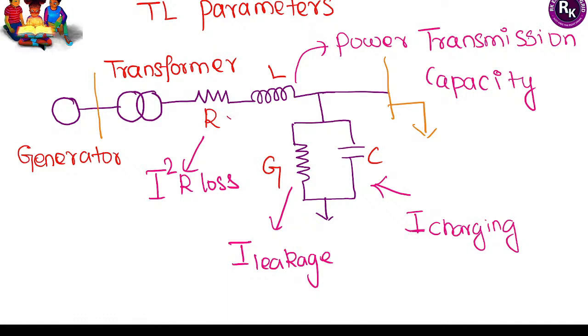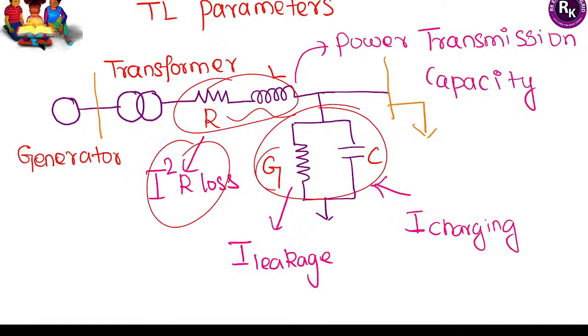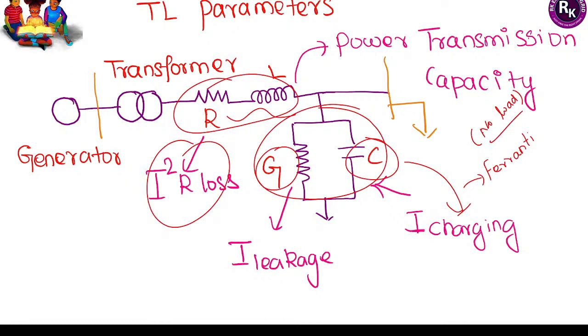Transmission line parameters: the equivalent circuit of a transmission line has four important parameters — series parameters (resistance and inductance) and shunt parameters (conductance and capacitance). Capacitance is responsible for charging current, which causes the Ferranti effect — where, even at no load, the receiving end voltage is higher than the sending end voltage. This Ferranti effect is clearly observed during no load and light load conditions. Series resistance causes I²R losses, decreasing efficiency.